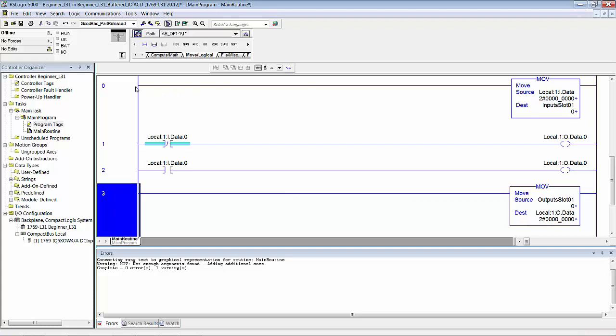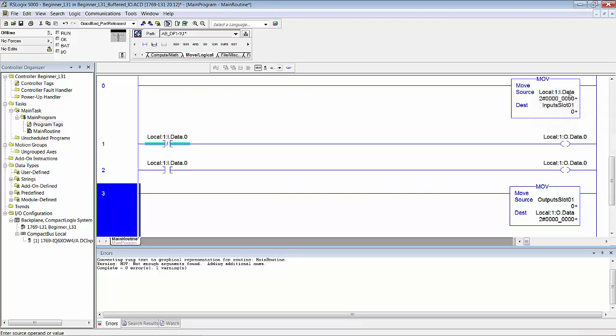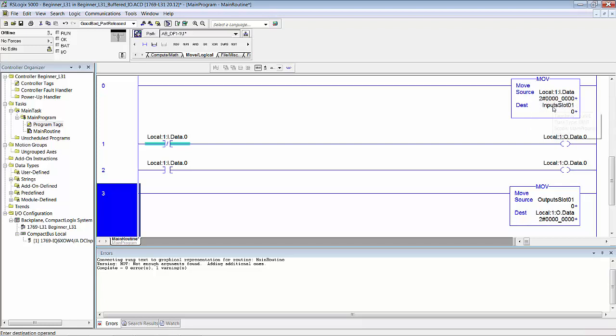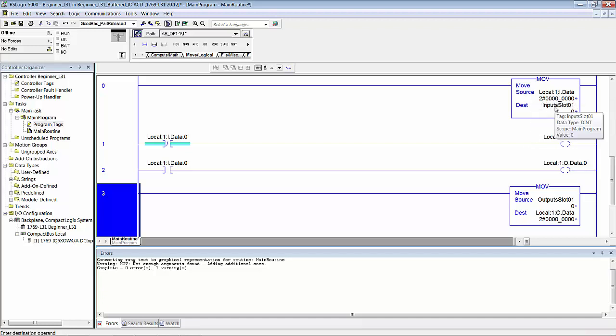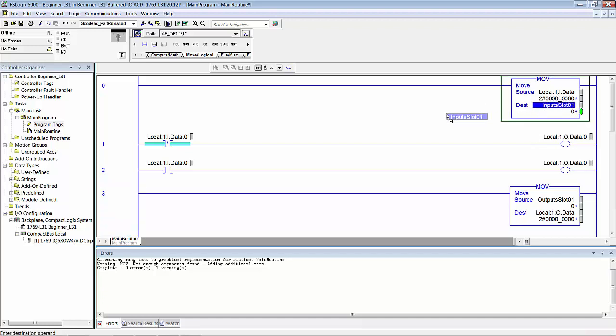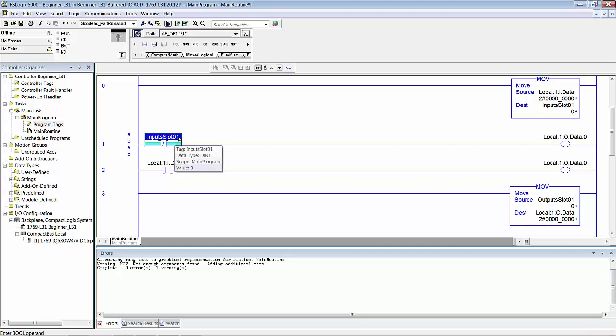Here we go. On the very first program scan, we take and copy whatever is in that input data memory location, we move it into this tag. Now we're going to use these tags right here—InputSlot1 for our inputs and these tags OutputSlot1 for our outputs. Rather than going through everything that we did in the manual, I'm just going to take and cheat here. I'm going to grab InputSlot1—I'm not moving this, I'm taking a copy of it over to here. And of course that's a double integer, we don't want a double integer.